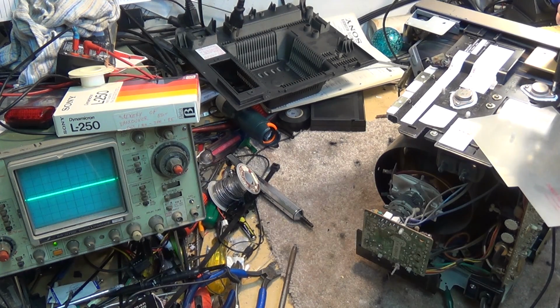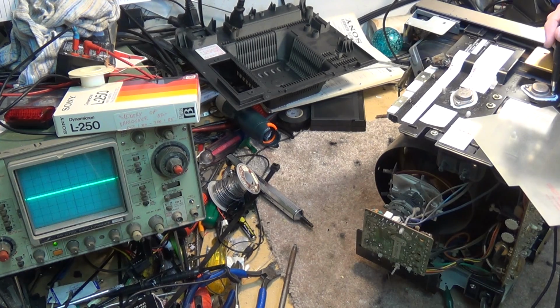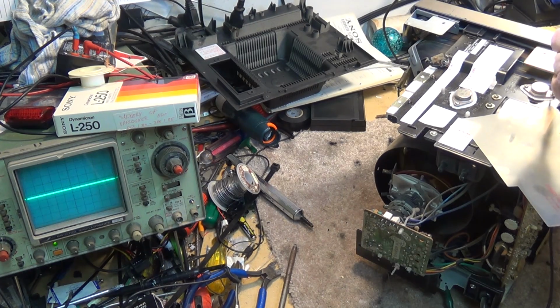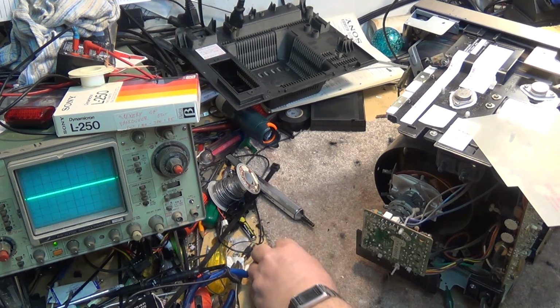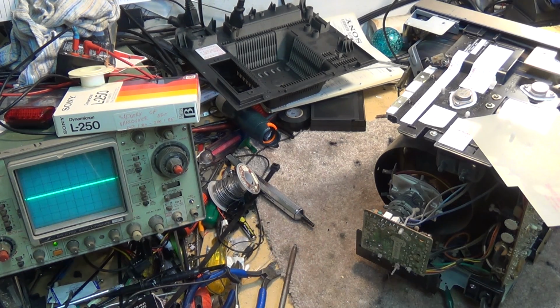Got to let this thing completely discharge. So it's going into shutdown. It's trying to start, and it's going into shutdown mode. We'll try that again. See, the pulse is there, and then it shuts off. So the set is trying to start up, and for some reason it's going into shutdown. We have a component that's failed, or the voltage is too high and it's going into over voltage shutdown.